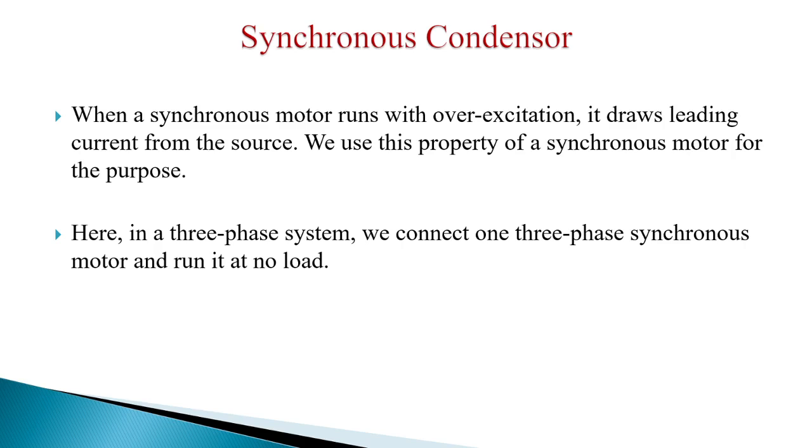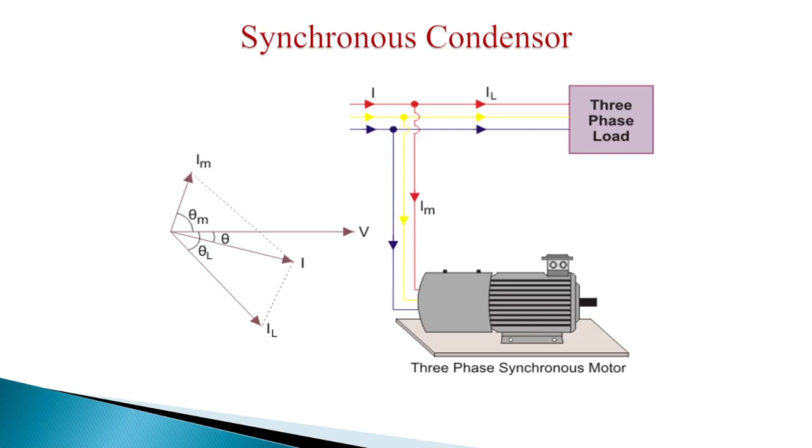Here, in a three-phase system, we connect one three-phase synchronous motor and run it at no load. In the figure you can see there is a three-phase synchronous motor and the three-phase load is connected to it, and there is a phasor diagram where V is taken as the reference, I is lagging V, and the angle between V and I is theta, and I will be the vector addition of IL and IM.